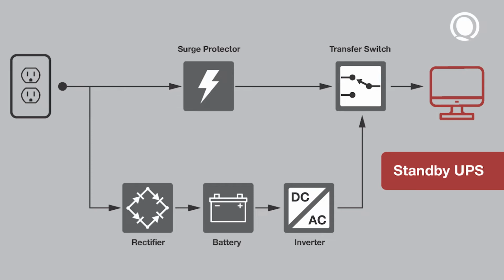And out of that transfer switch, it goes to your computer, your monitor, whatever device you're trying to keep up during the power outage. Along with that, the AC that's coming in is going into something called a bridge rectifier. That bridge rectifier is used to charge a battery. And that battery then drives some type of an inverter that gives you an AC signal out, and that signal then goes to the transfer switch. If we lose power, the transfer switch is going to kick over, the inverter is going to kick in and provide power to your device.